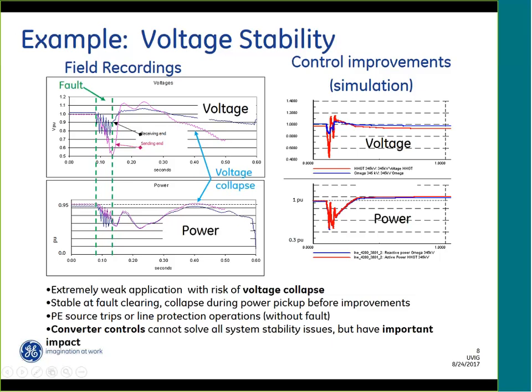What are the characteristics of this? Well, there are many things here that are similar to the same voltage stability that has been studied in power systems for so many years. Basically, we were trying to push more power, and we didn't have enough reactive power available to sustain that power transfer in this case. The characteristic of wind turbines is that the power pickup occurs in 200, 300 milliseconds. So the voltage collapse also occurs in 200, 300 milliseconds. That's a characteristic of voltage collapse with renewables. If they happen, they tend to be somewhat faster than maybe what we are accustomed to seeing in power systems 10 years ago.